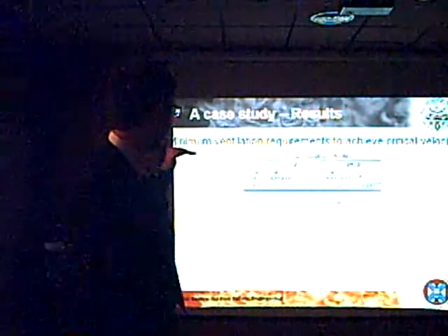So we took our tunnel and looked at the minimum ventilation requirement to achieve critical velocity within our tunnel. First we did just a one-dimensional calculation, with different fire sizes, and then we did the same calculation but adding the additional pressure losses we calculated using the CFD model. What we saw is that the flow resistance and the buoyancy of the fire are not negligible at all, and in our case, with our ventilation system, the traditional one-dimensional model calculation underestimates the ventilation required for the worst case scenario by up to 40%.